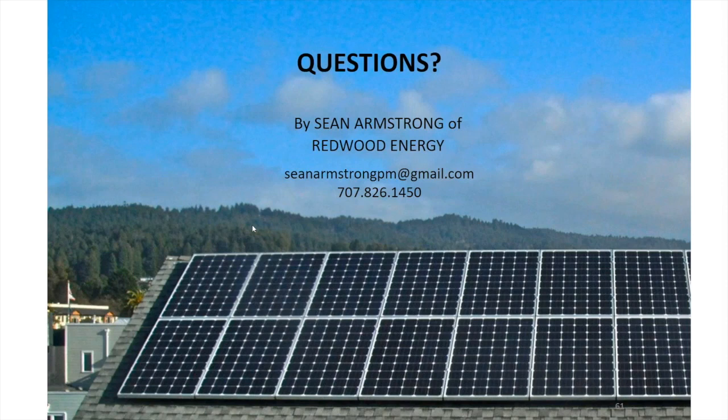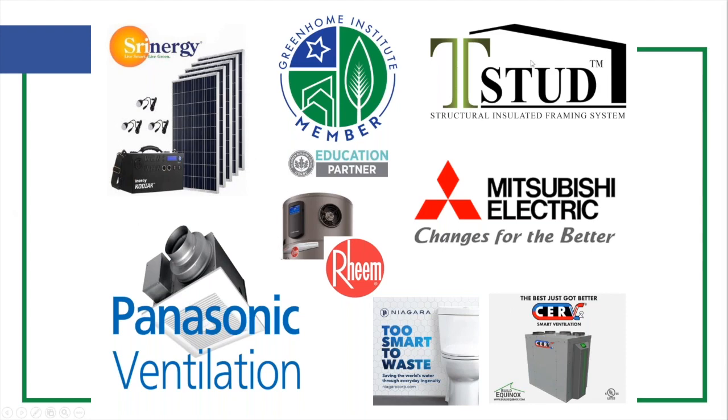Well, I'd spent about a year studying all the states in the United States with one of my engineering staff. So I did a massive analysis of all the different rates for each state, the gas versus electricity. And in most states you can get there with about 200% or 250% efficient heat pumps, which is the federal minimum, as long as they work in the wintertime, that's the main thing. If they have an inverter, they actually keep that efficiency during winter as opposed to converting to electric resistance. So you're seeing products like Mitsubishi, for instance, bragging on the fact that they operate down to negative 22 degrees Fahrenheit still as a heat pump, and that's what you're looking for.